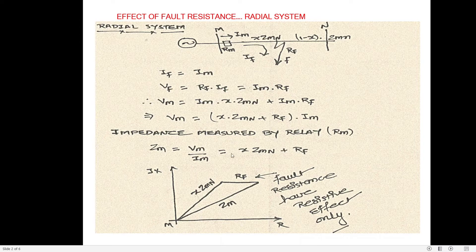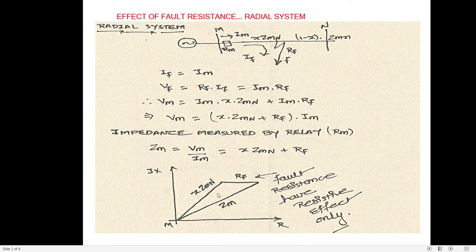X·ZMN is the fraction of impedance up to the fault point. When the effect of RF is not considered, the total impedance measured by the relay is only X·ZMN, and the relay operates correctly. Any characteristic — circular, plain impedance, or offset mho — works in that case. But once the effect of RF is introduced, the impedance measured by the relay increases depending on the magnitude of the fault resistance.